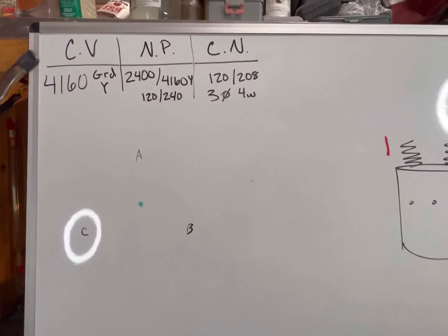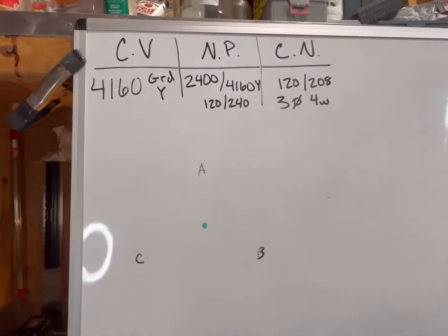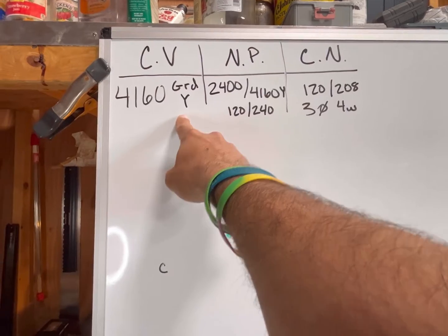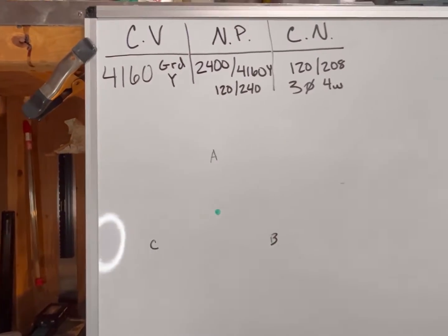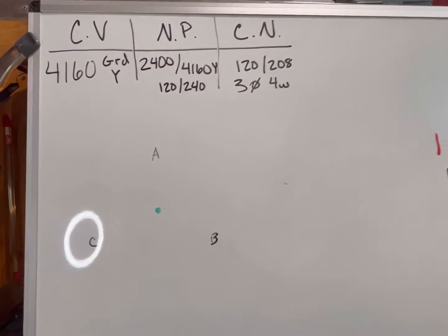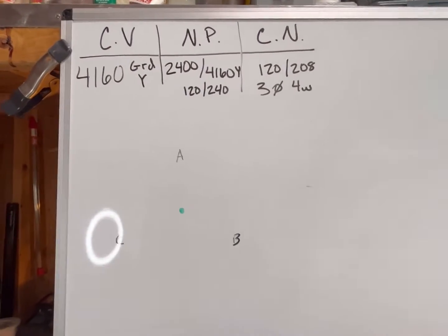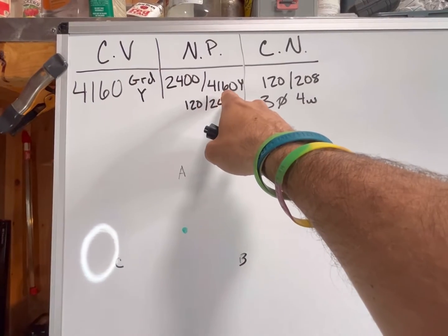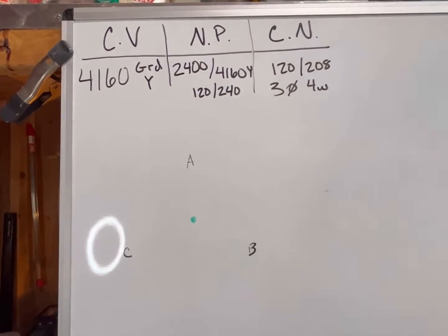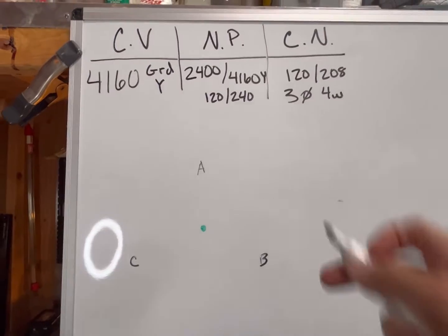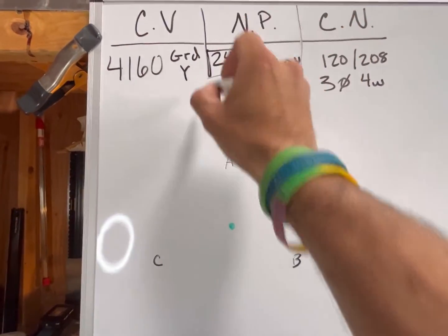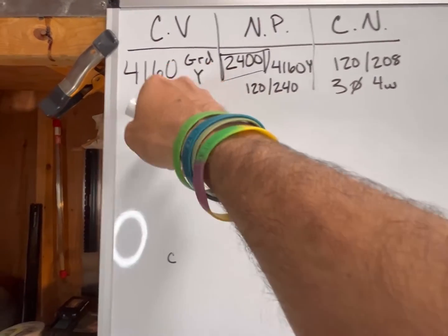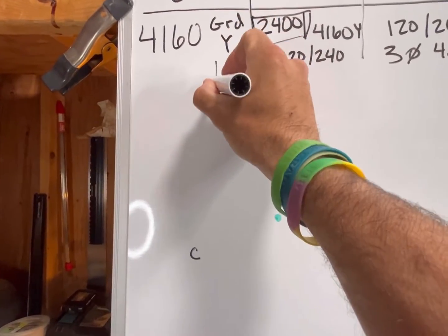For everybody familiar with this, you can see I've picked a Y circuit — I've got 4160V. I picked a grounded Y, just because that's what I had out there. It can be an ungrounded Y; it doesn't matter. But for this example I went with a grounded Y. My nameplate is a 2400/4160Y, 120/240 secondary, which means the transformer is going to need 2400 volts, so hooking it up on this circuit is going to require a Y hookup.